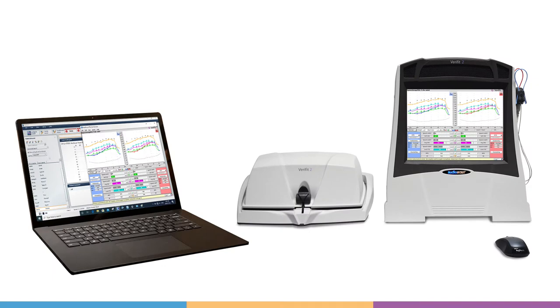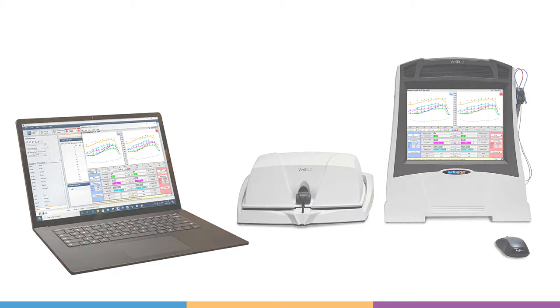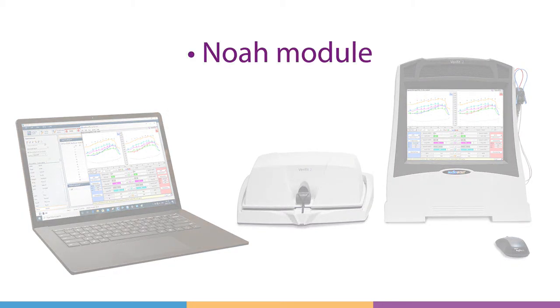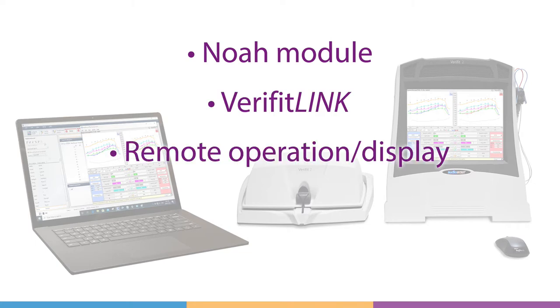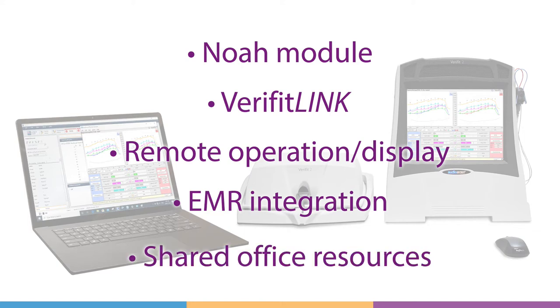Networking your Verifit2. There are several reasons you might want to connect your Verifit2 to a PC network: to run the Audioscan NOAH module, to automate hearing instrument adjustment with Verifit Link, to view and operate the Verifit from your PC screen, to save PDFs to a location where they can be read by your EMR software, or to access network resources such as office printers.